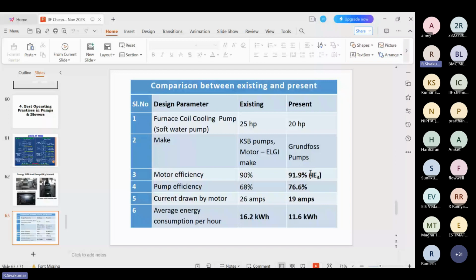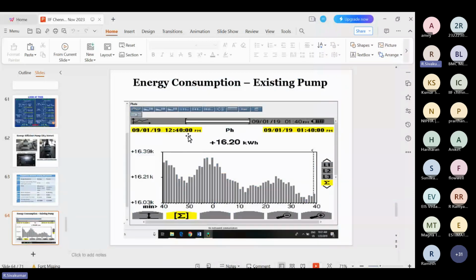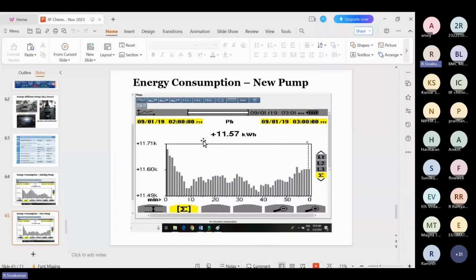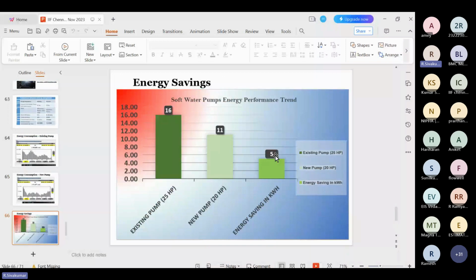See, another thing is pump efficiency is 68 for the old one. The new one is 76.6. The average energy consumption per hour is 16.2 units for the old one. The new one is 11.6, almost 4.8 units can be saved per hour. This pump is running continuously for 24 hours. The power analyzer reading was taken on the 9th, 2019, during the project time in the company. So in 1 hour the old pump was consuming 16.2 units. The new Grundfos pump is taking only 11.57 units. What is the impact? Almost 4.8 to 5 units can be saved with the new energy efficient pump.